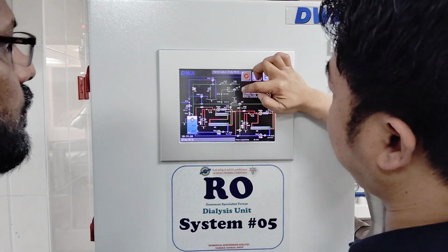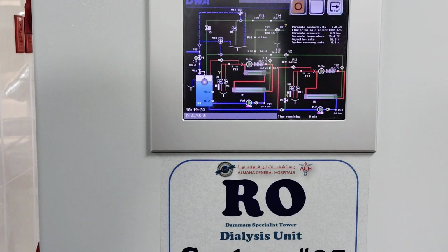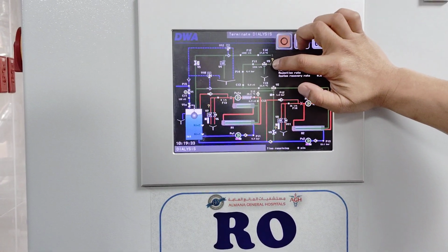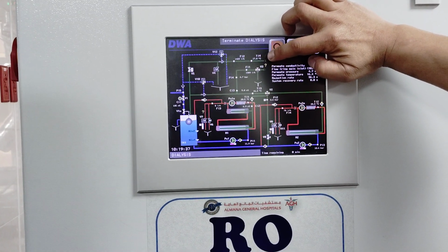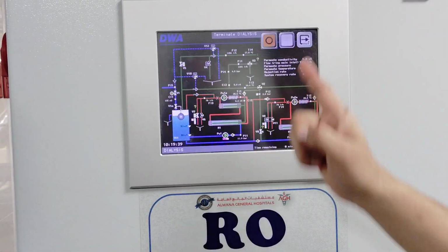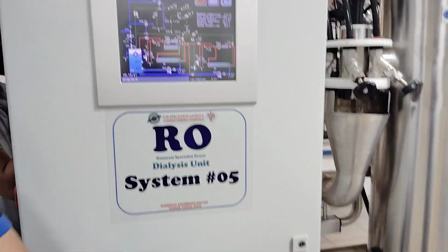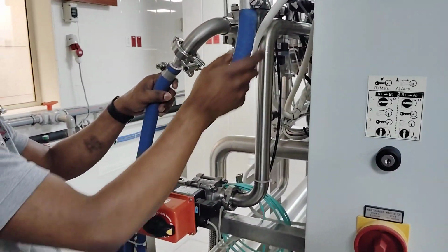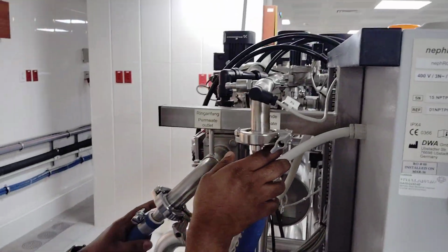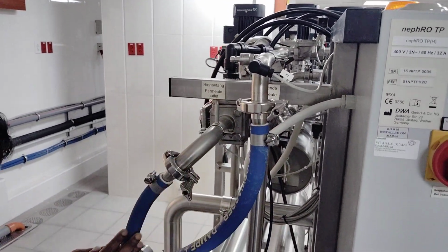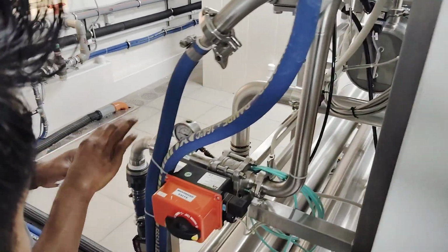Okay. So this is the input going to the area. Dialysis room. Dialysis room. Yes. And this one is the return from the dialysis room. That is considered here like this one. This is the input. Okay. This is the output. This is the return. Okay. This return means it's going back to the membrane. This is the output, RO output, going to the patient area.